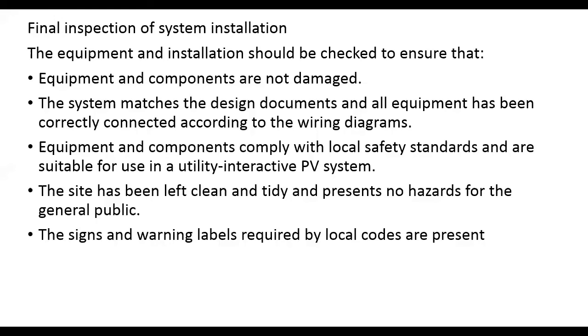Okay, all those things have to be monitored, such as whether any roof penetrations are properly sealed and whether weatherproofing has been done, when we are checking the component, that is, the PV array. And not only that, the inverters should be inspected, of course, prior to commissioning. Before we commission the complete plant, the inverters have to be inspected to see whether the electrical connections, in and out, have been made properly with respect to all of the units, and whether the location of the inverter is suitable. As we discussed in the previous chapters, the inverters have to be properly placed in a closed area and should be easily accessible. Okay, those things have to be monitored.